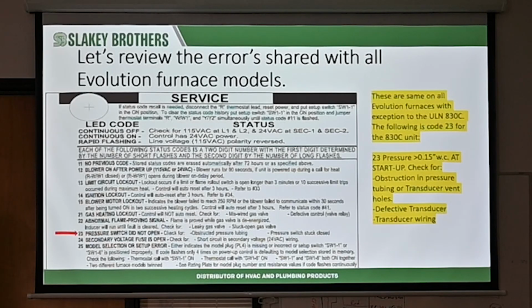So let's say your unit's running, and the utility has a power outage for, hell, 10 seconds, whatever it is. Even if it just shuts off for like 5 seconds, 10 seconds, the unit shuts off and comes right back on, that heat exchanger is hot. So because it sensed that it was asking for heat immediately, as a safety measure, instead of turning on the burners again for 30, 40 seconds before the blower turns on, it purges first for 90 seconds and then allows the heater to turn back on again. Okay, limit circuit lockout. Actually, that's going to be 33 first. We're going to come back to that one.